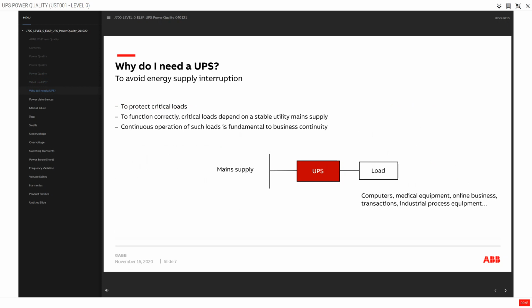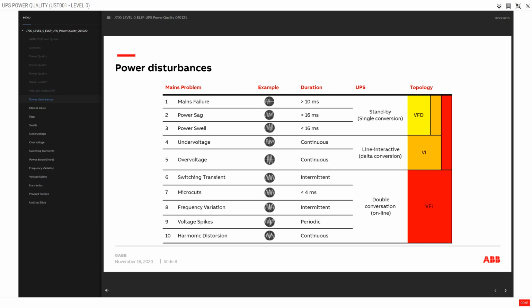To protect critical loads. To function correctly, critical loads depend on a stable utility mains supply, to provide continuous operation to loads that are fundamental for business continuity. Below is a list of utility power disturbances. Mains failure. Power sag. Power swell. Undervoltage. Overvoltage. Switching transient. Microcuts. Frequency variation. Voltage spikes. Harmonic distortion.